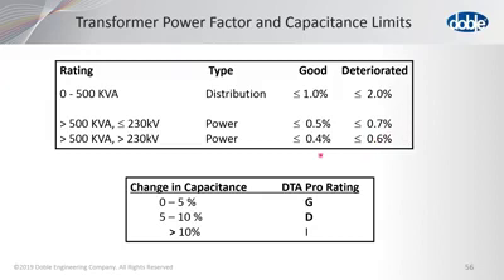Now, I had mentioned that the change in capacitance is very, very important. Between 0 and 5%, you'll get a G rating, you won't notice. Between 5 and 10%, we will get a D rating. Even if all the power factors are good on a particular insulation, if it's between 5 and 10, you will get a D. And if it's greater than 10% change, you'll get an I rating.